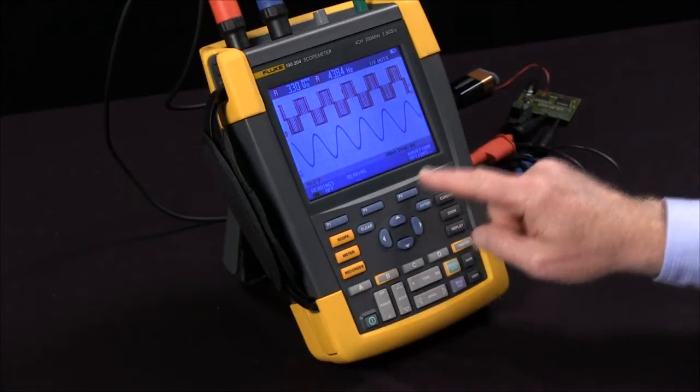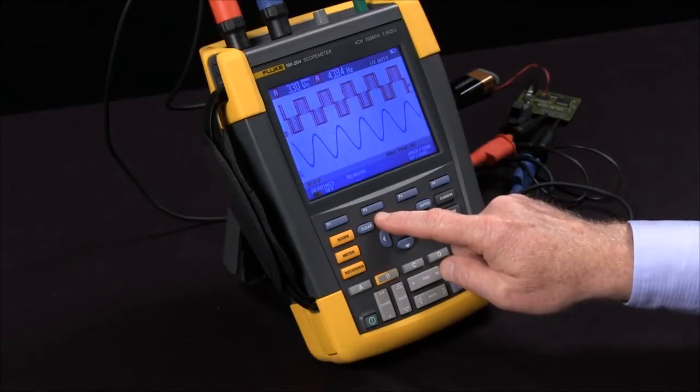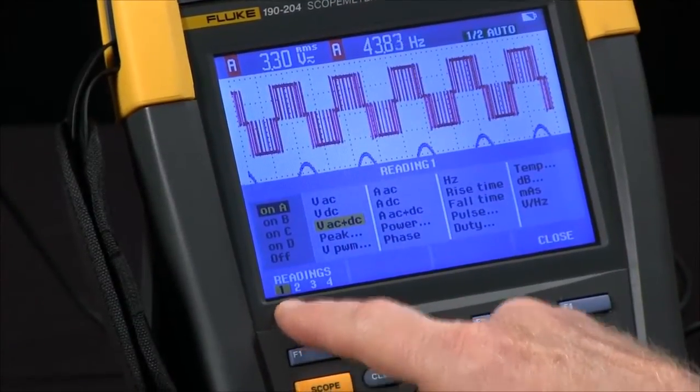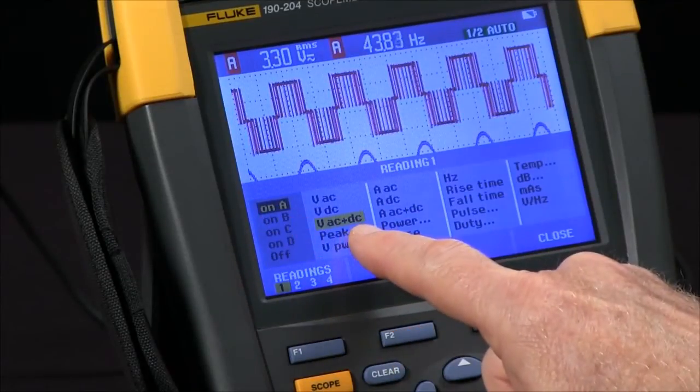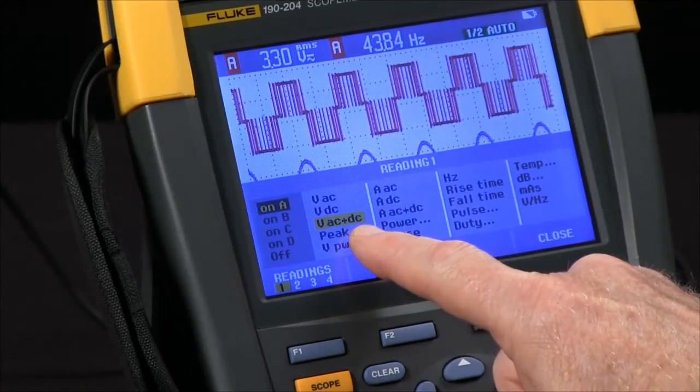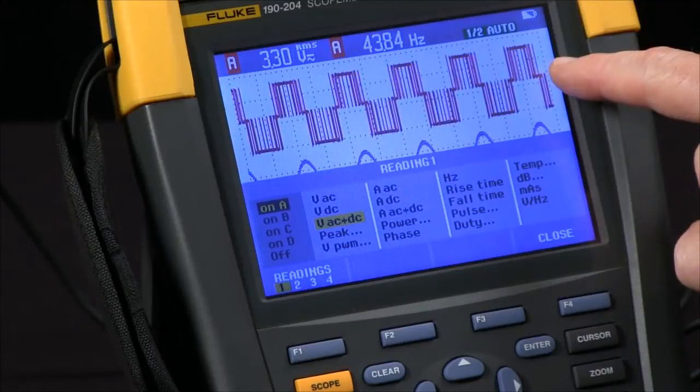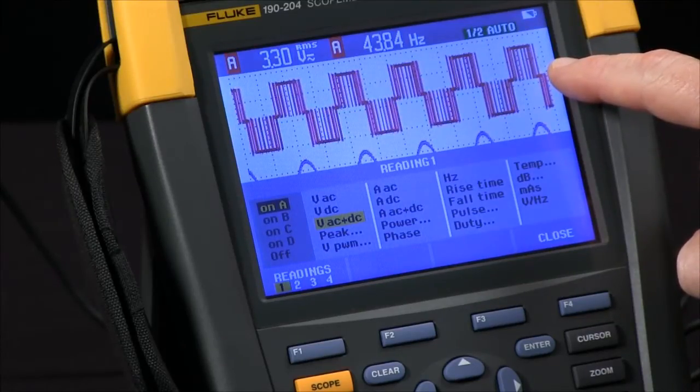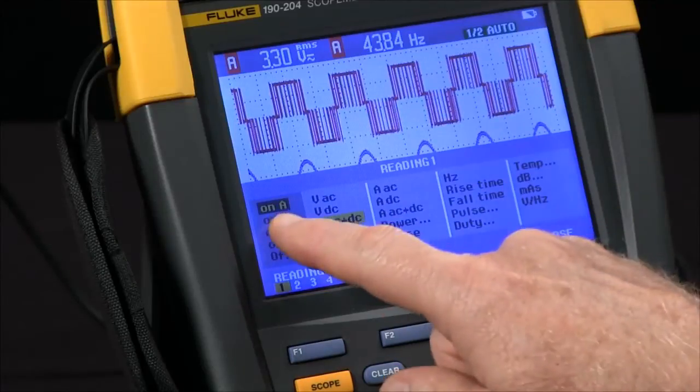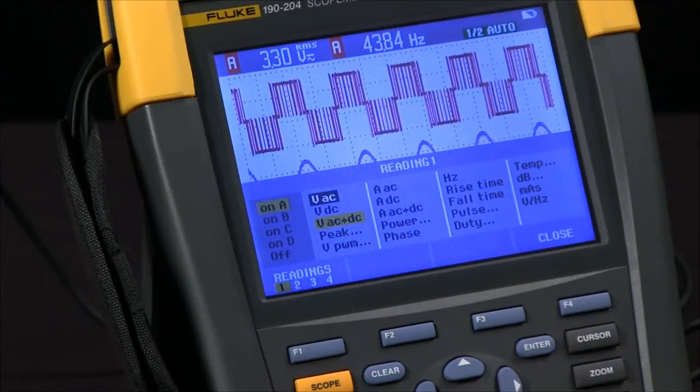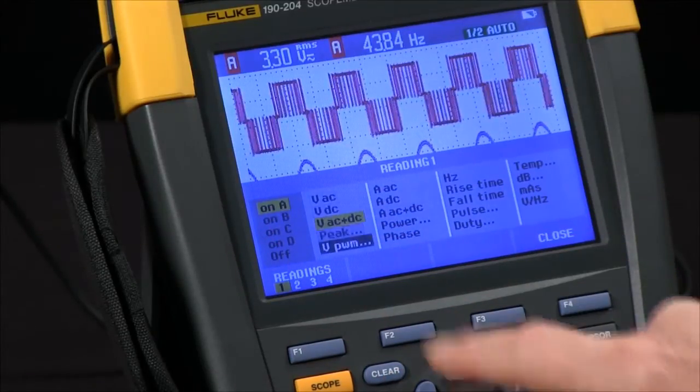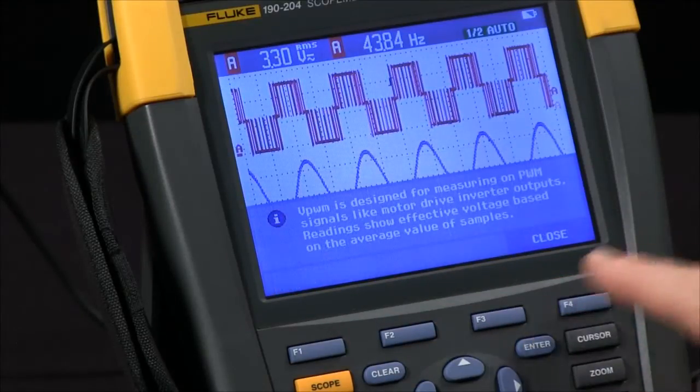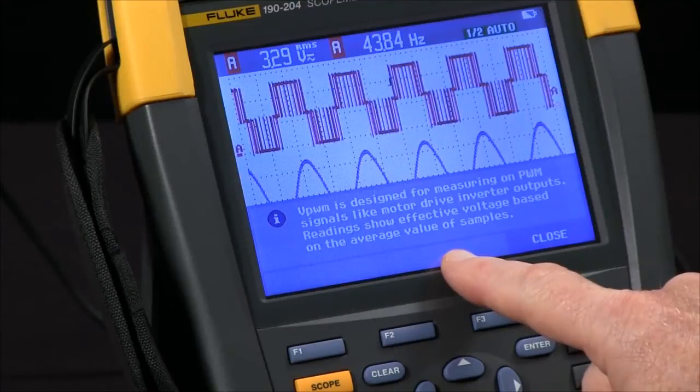To modify those I hit the F2 button for readings. Right now reading one is on channel A reading volts AC and DC. I want to measure VPWM for this since it's a variable frequency drive signal, pulse width modulation. I'll use the arrows to move channel A, highlight VPWM, hit enter. It describes the measurement for motor drive inverter outputs.